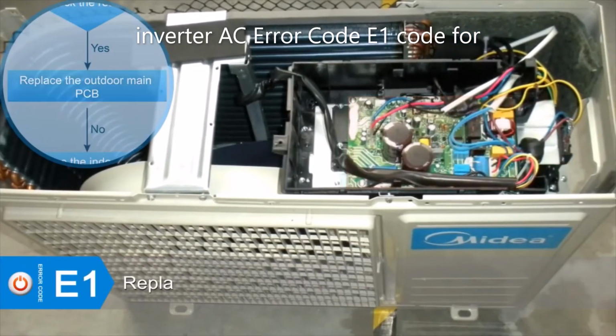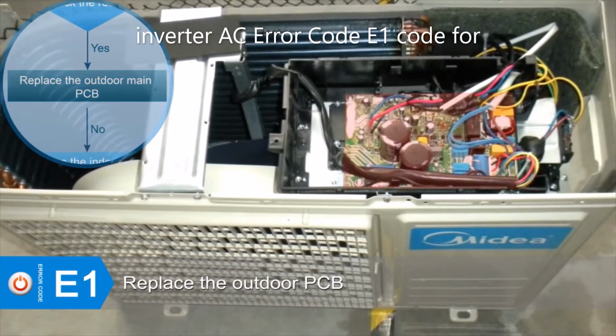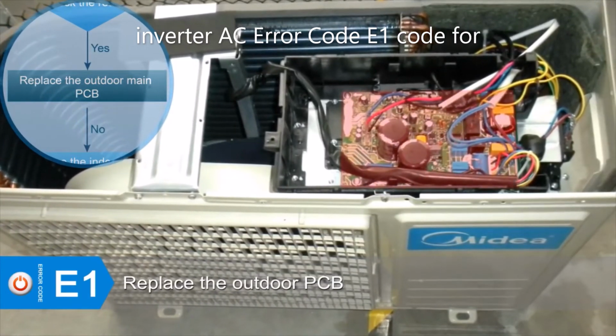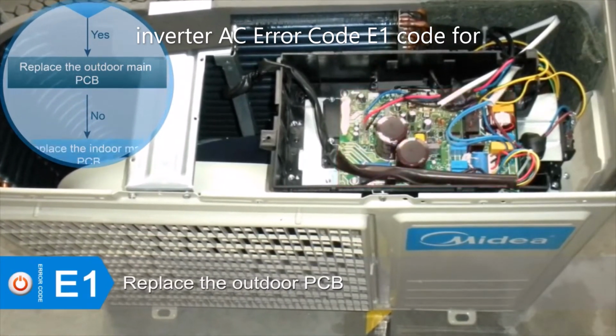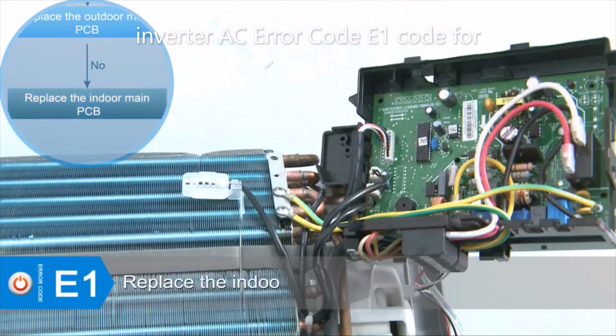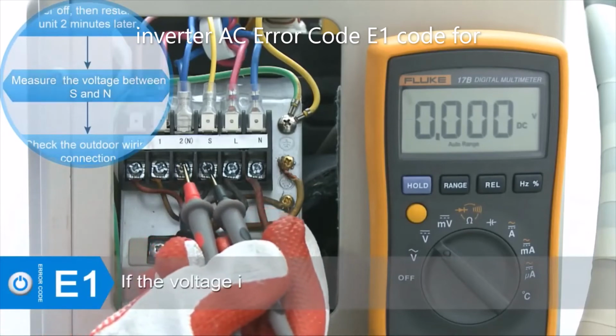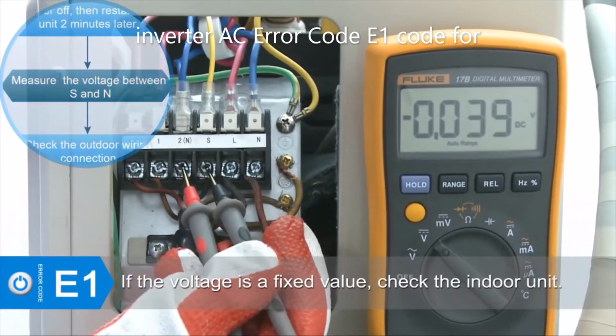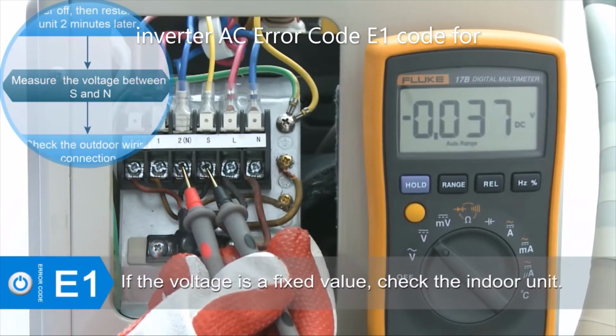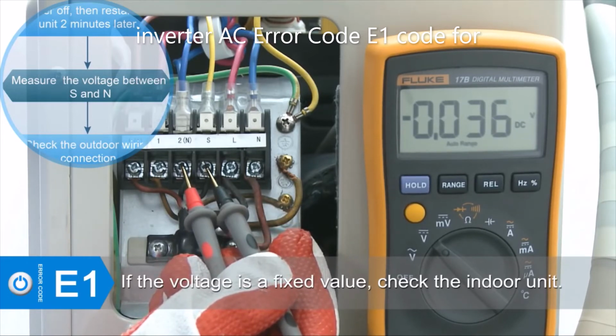If the error still exists after the maintenance procedure above, replace the outdoor PCB. If the error still exists, replace the indoor PCB. If the voltage is a fixed value, possible malfunction should have occurred on the indoor unit. Main attention should be paid to the indoor unit.